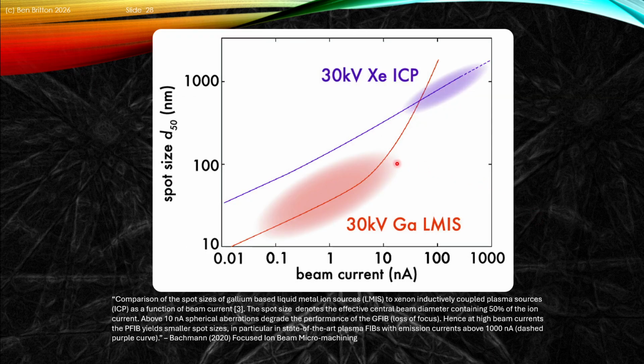Why do we use these different systems? We'll see a few things a bit later, but one that's important is that we can look at the so-called spot size, the D50, so that's 50% of the ions will be within this size. We can do this based upon the beam current of our system. Typically for most gallium systems, there is a sweet spot of a beam current between, say, 100 picoamps, or down to 10 picoamps, up to, say, 10 nanoamps or so. And here we get a relatively linear spot size with current domain.